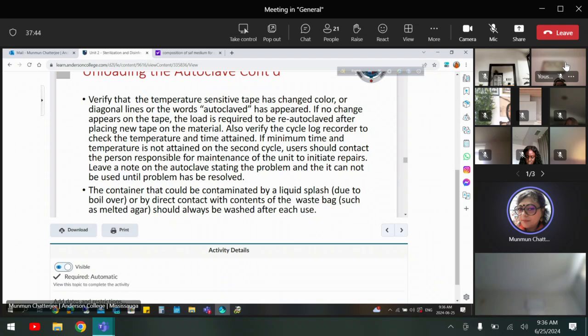So in your first autoclave run, you say it didn't work, the tape didn't change. Then you run the second cycle, and you watch whether it is running for the minimum time and, most importantly, whether the temperature and pressure have been attained. If it is not reaching 121 degrees centigrade and 15 psi, then that means the autoclave is not functioning properly. You cannot do any manipulation or take care of anything regarding the autoclave. Contact your lab manager or your senior, and then they have to contact the maintenance.